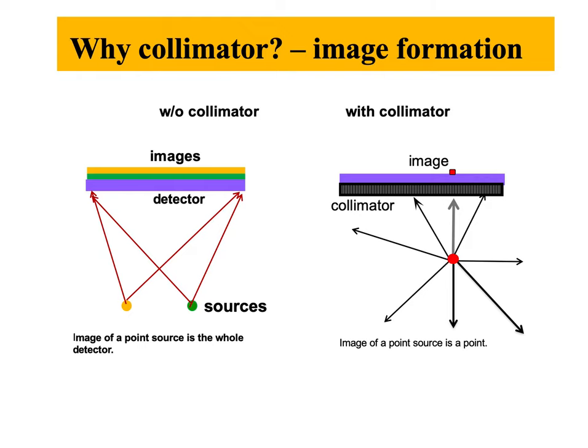The crystal will not be excited from anything that is not immediately beneath it. If we don't have the collimators and we have two different sources, we get signals from different locations, creating blurriness and non-specificity in the image. This is why we use collimators — we want to make sure we are looking at the image of a point source in the specific location inside the subject, so we can identify that location precisely.